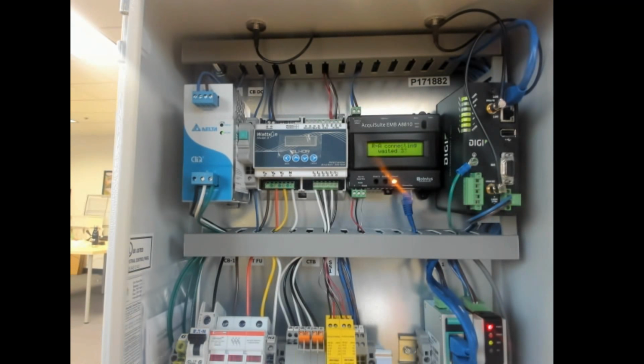So especially for support, if you have a customer who says, hey, I have the CT, it says 5 amps, and you know the LGate 360 build has a Veris, watch out - that Veris might power on, but all the measurement circuitry inside the meter will no longer work. So something to definitely be aware of.